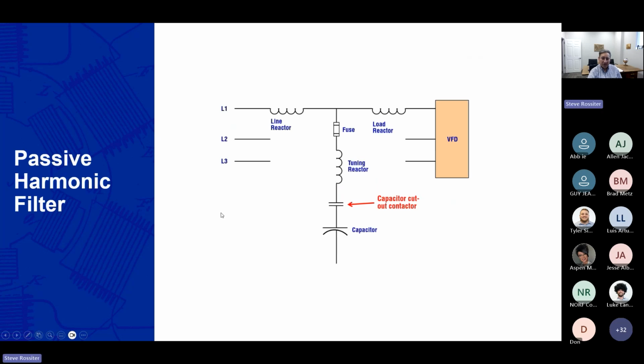Passive harmonic filters, this goes back to that patent that we developed, where now you have a tuned circuit here with a capacitor and a reactor that is trapping the fifth harmonic or the frequencies that we tune to into this trap, so with a little bit of impedance here, it's not going out onto the line. That's the standard art nowadays. Our patent, we licensed it to a number of companies that used it until the patents ran out 20 years later, and now everyone has a technology with slight variances on that.